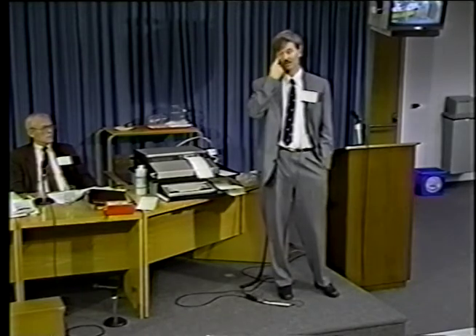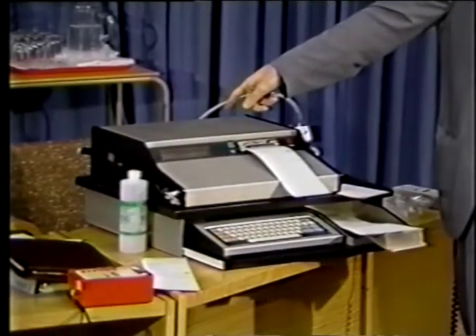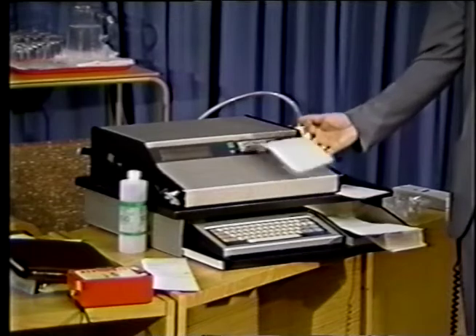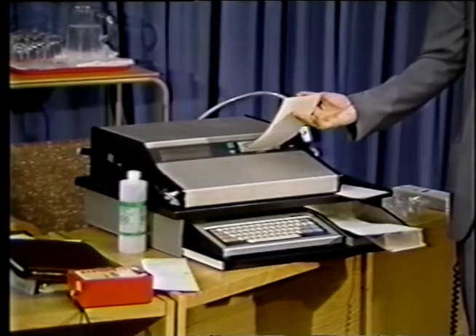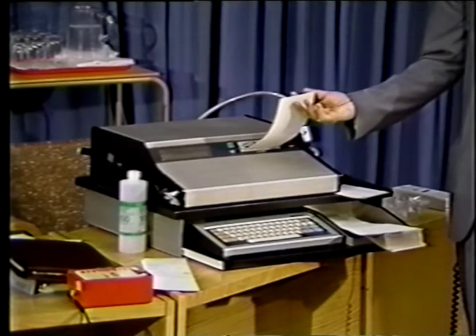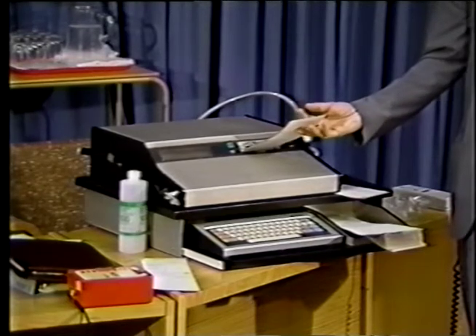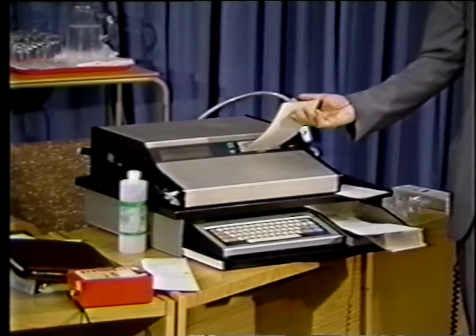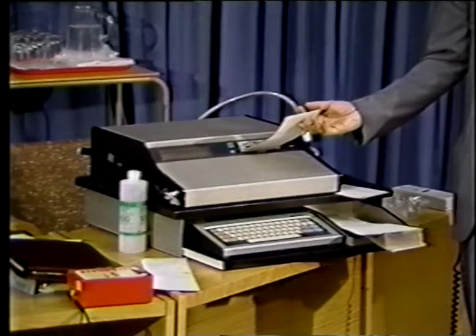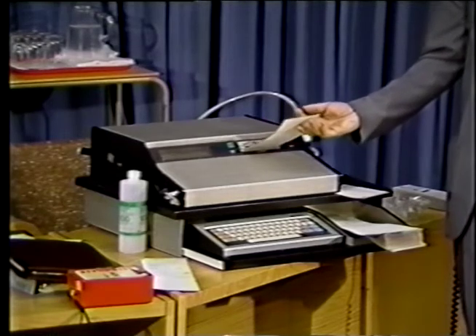Oh, yes, you'll do the mouthwash, too. And lastly, all the results are printed. So all the data I entered about the name and that will be printed. Also the results of the blank test, the calibration check, the blank test, and the subject test will all be printed out. And what will happen is 15 minutes later, this procedure will be repeated, and the other side of the card will be inserted. In between, you can do another 3 subject tests because there's no ampules to change, no nothing. It's all ready to go again right away from the first test.